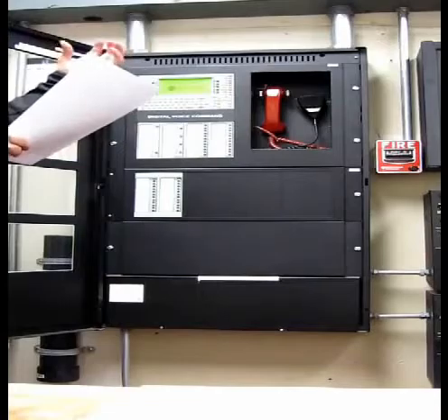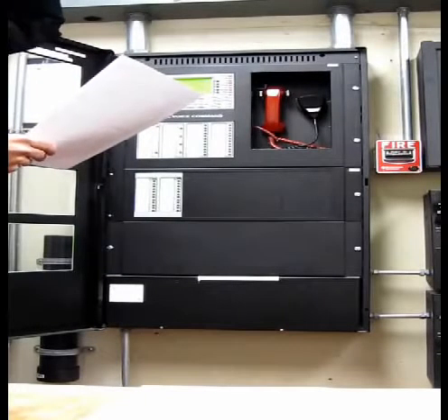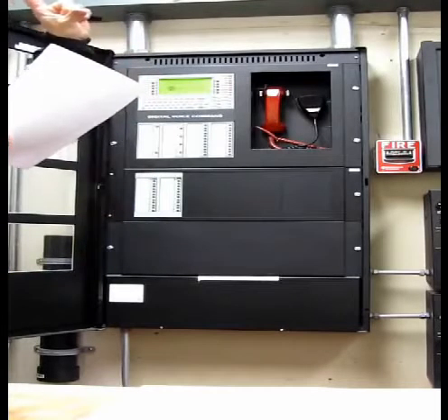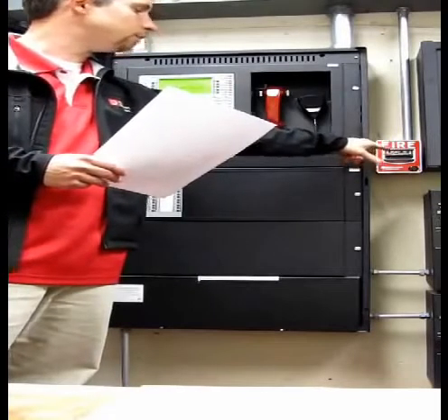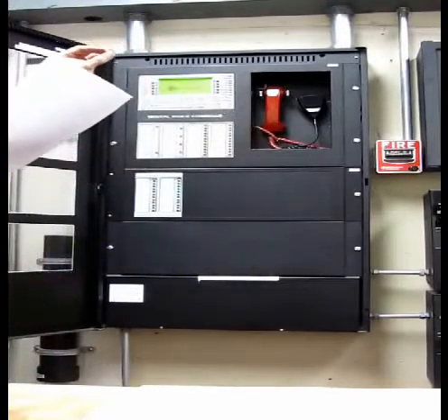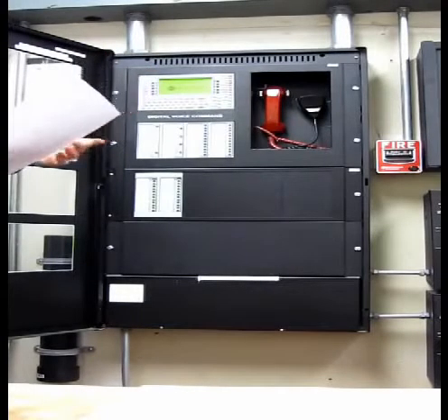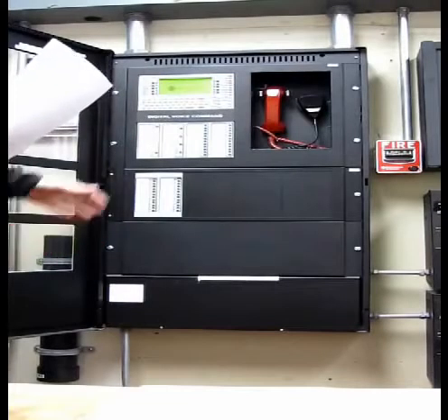Also, when a device goes into alarm, it has a solid red light. Right now, if you watch the one above it, it's going to flash about every 6-7 seconds. It flashes green. When it goes into alarm, those two LEDs will lock in red. Same thing with the pull station. You can see the little flashing green light behind it. Once you pull it, that light will flash red, or stay solid red. So that makes it easier too when you're walking down the corridor to find out where the device actually is. So you have the description on the panel plus the LEDs to help you.